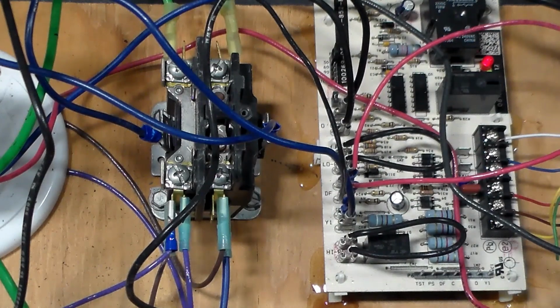There is an L terminal on here. On this particular board it's not used. On most boards it's not used. So I'm going to leave that out today. But our C terminal, of course, our 24 volt common, typically your blue wire. And then we have our white wire, W1, which, as we know, that is typically heat. But on a heat pump, the heat pump's your primary heat. So why do I need that stinking white wire out here to control the furnace heat when the heat pump's supposed to be doing all the heating? I'll talk about that in a minute.